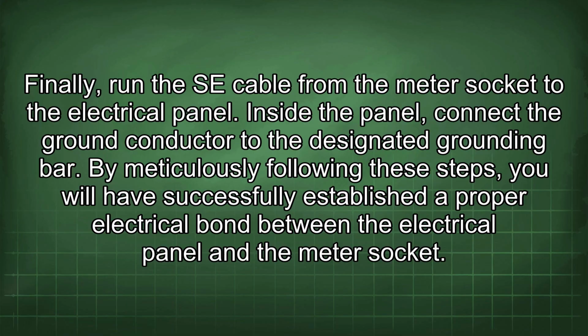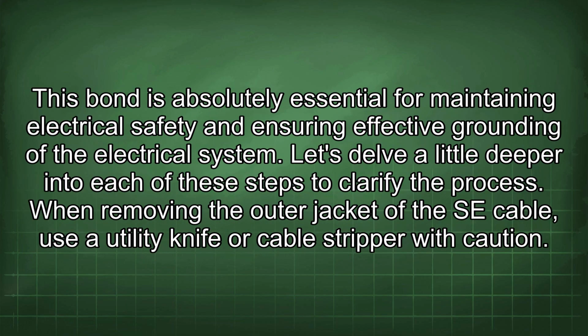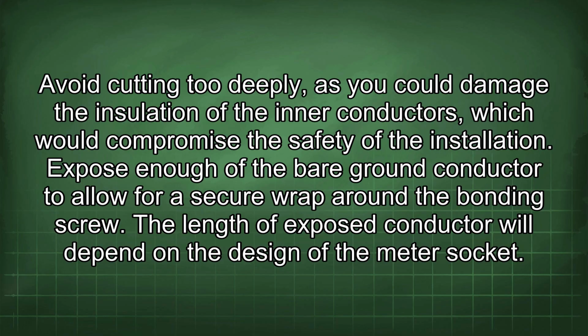By meticulously following these steps, you will have successfully established a proper electrical bond between the electrical panel and the meter socket. This bond is absolutely essential for maintaining electrical safety and ensuring effective grounding of the electrical system. Let's delve a little deeper into each of these steps to clarify the process. When removing the outer jacket of the SE cable, use a utility knife or cable stripper with caution. Avoid cutting too deeply, as you could damage the insulation of the inner conductors, which would compromise the safety of the installation. Expose enough of the bare ground conductor to allow for a secure wrap around the bonding screw.